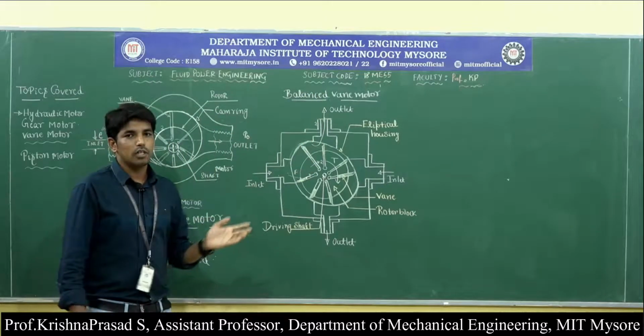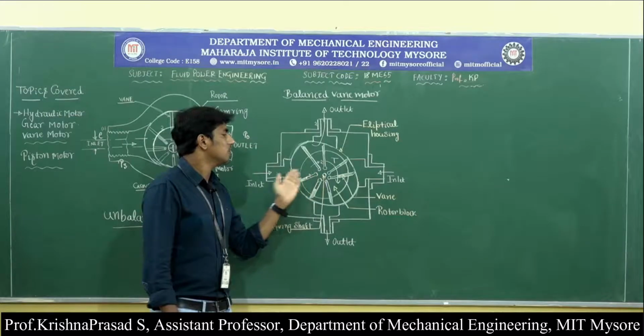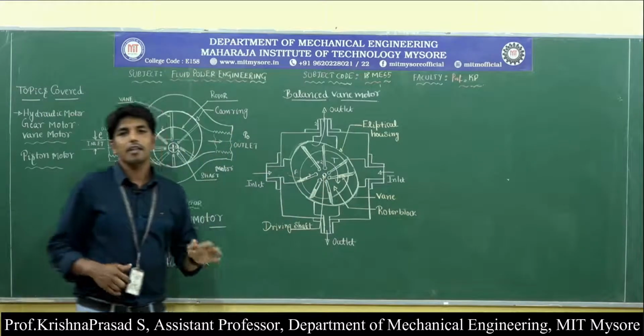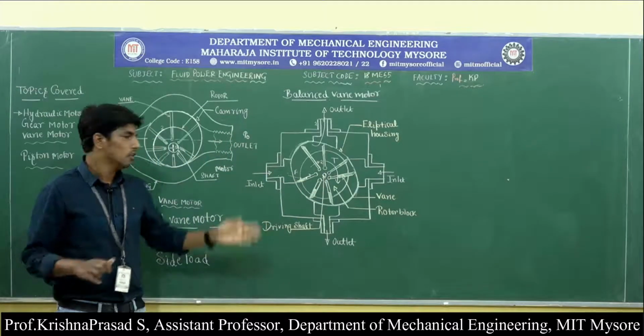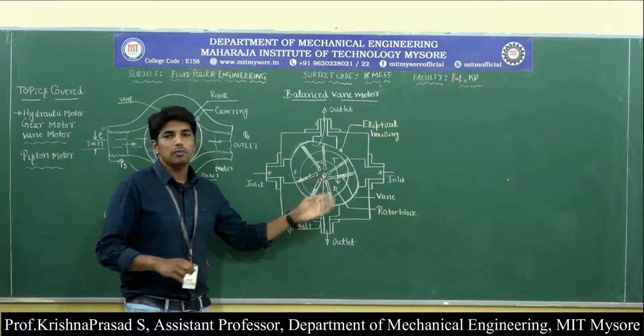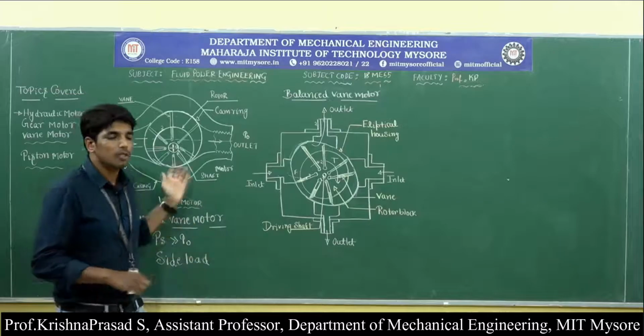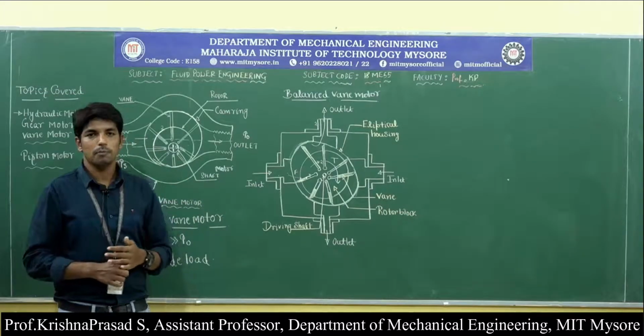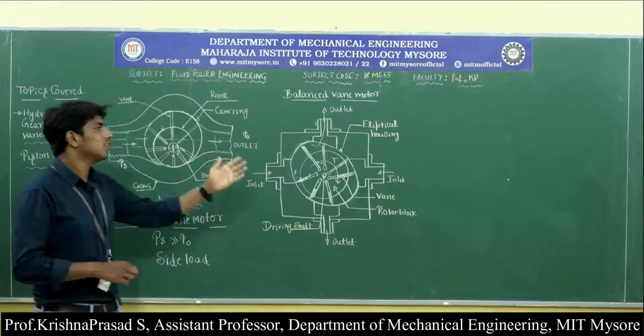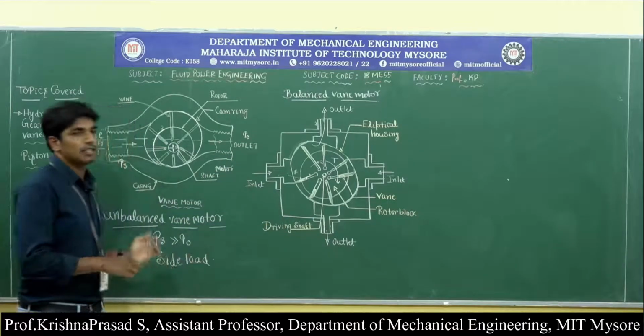And a very important one is that the elliptical housing and the axis of the rotors are the same, hence the side load is going to be nullified. As well, a very important thing is that it is going to provide better service life compared to the unbalanced vane motor. That's why we prepare the balanced vane motor compared to the unbalanced vane motor.